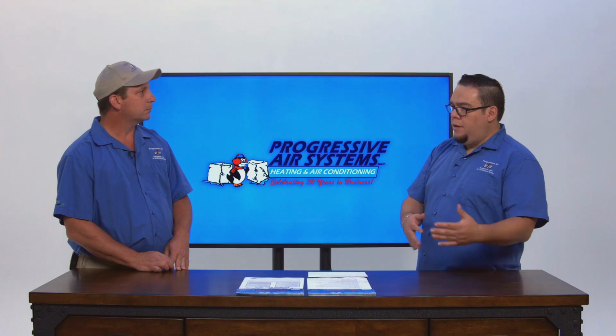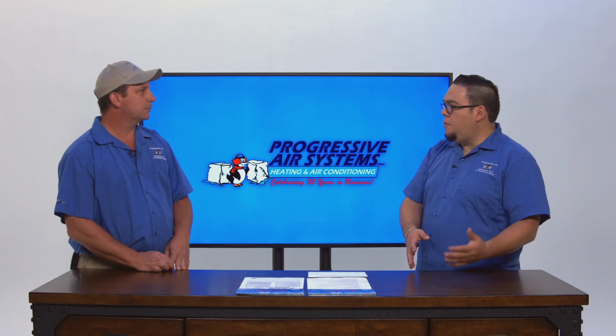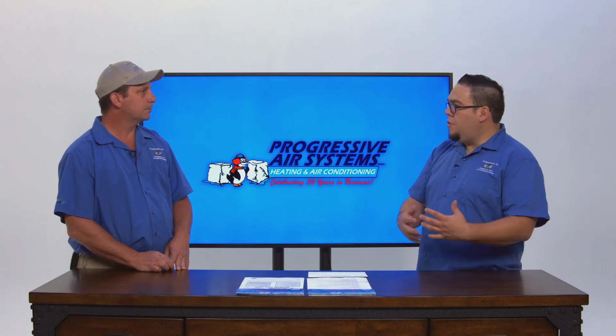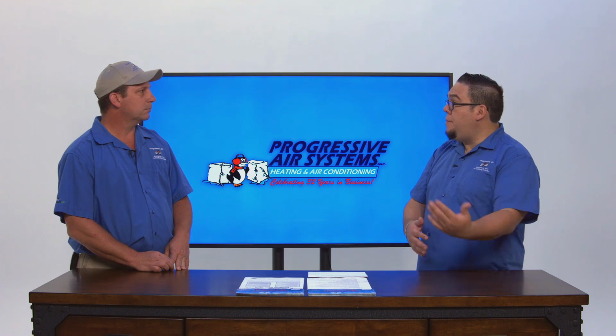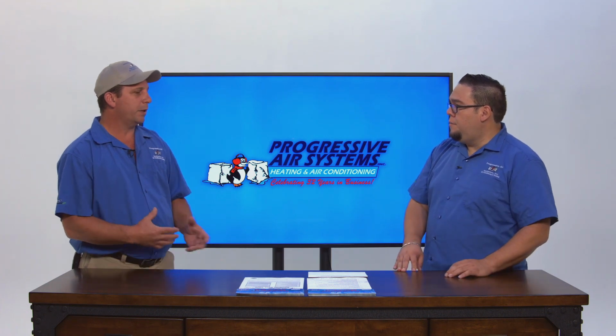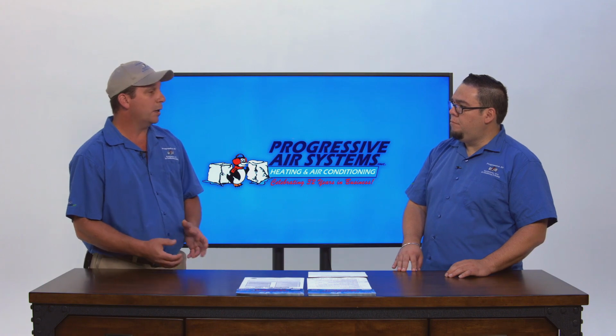Okay. Now, when someone comes out on a maintenance plan and looks at my unit, are they able to identify some smaller issues that may become larger issues? Absolutely. When we come out to do regular maintenance for a homeowner, we check what we call the vitals. That's the refrigerant charge of the system when it's in heating or in cooling. We also check the amps. We check the capacitors to make sure they're within factory range of that rating on that capacitor. We check the amp draws. We check the safety float switches. Those are most critical, especially in a cooling cycle. Sure. A lot of damage could occur if those switches failed.